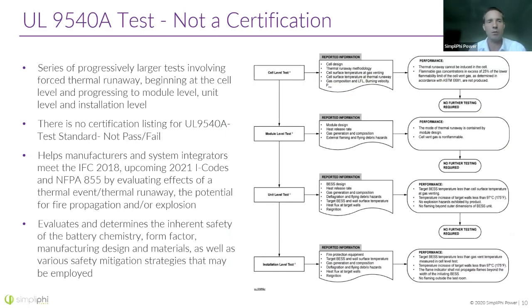I'm not going to take you through all of this, but basically the 9540 test is a series of progressively larger tests. We start at the cell design, look at the behavior of the cell, and put it into thermal runaway to make sure it doesn't explode. If the cell performs properly and shows no indications of being unsafe, no further testing is required at that level, and the cell can be used to produce modules certified under 1973.